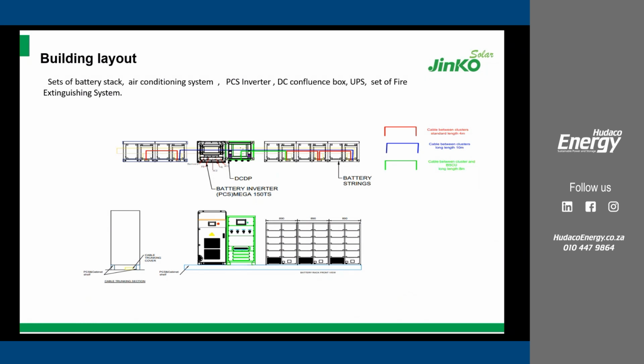What we need to pay attention to is that ideally the cables from the DC cabinets to each of the battery racks must be equal. They must be the same length of cables. That is one thing that we need to pay attention to as well. So ideally, it will determine how we do the planning of our building.